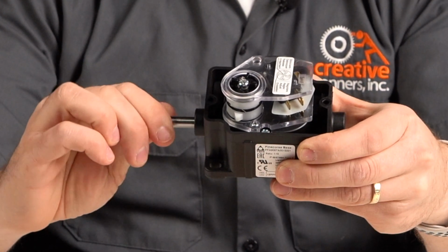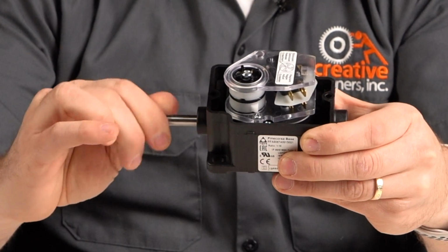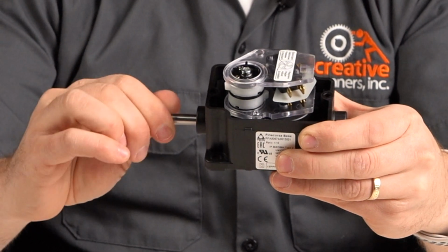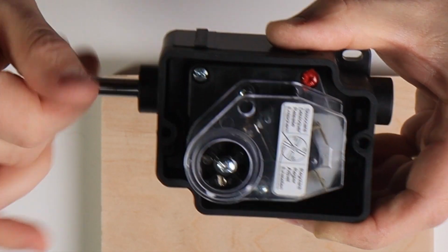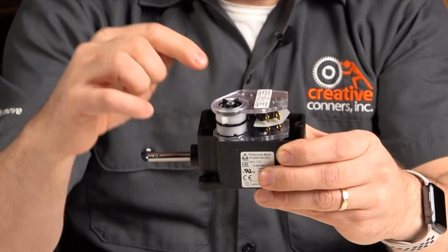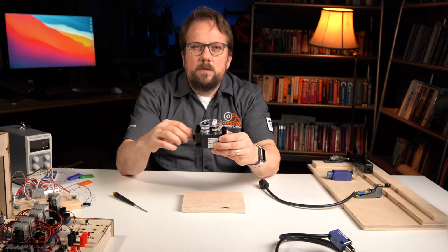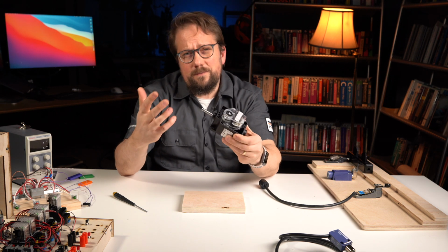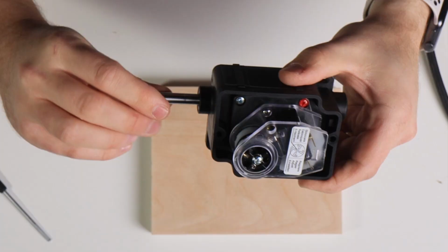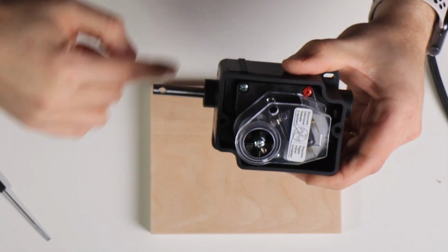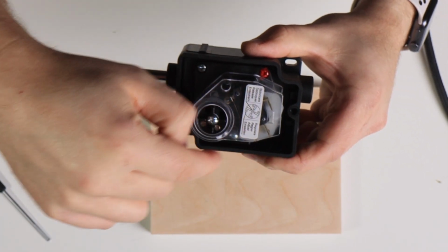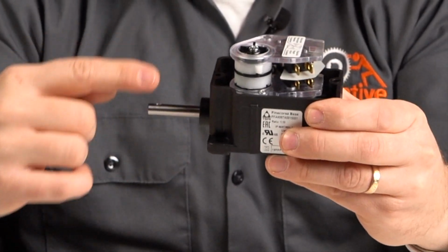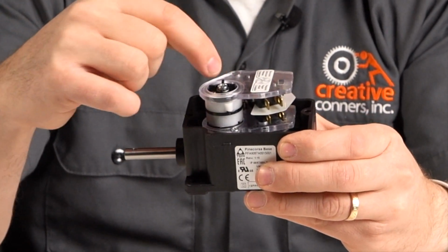The input shaft is geared to the cam stack so that as I rotate the input shaft, the cam stack rotates. The cams contact the micro switches. The full range of the switch is one rotation of the cam stack. You can spec the gear ratio between the input shaft and the cam stack. Say something like 15:1, meaning that it takes 15 revolutions of the input shaft to turn one revolution of the cam stack. Or 100:1, meaning it takes 100 revolutions of the input shaft to turn one revolution of the cams.